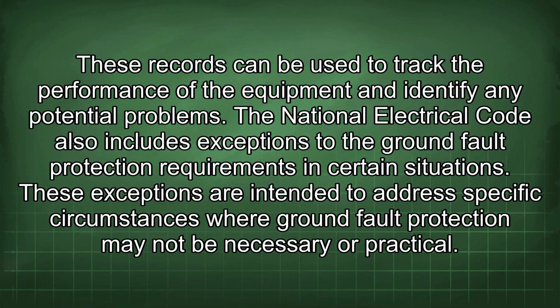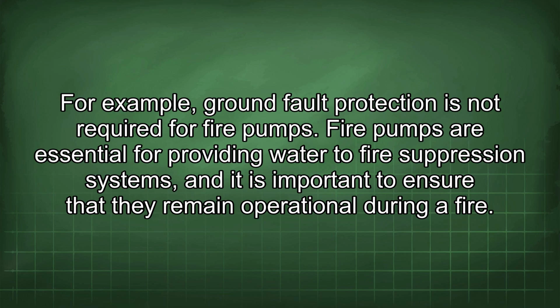The National Electrical Code also includes exceptions to the ground fault protection requirements in certain situations. These exceptions are intended to address specific circumstances where ground fault protection may not be necessary or practical. For example, ground fault protection is not required for fire pumps.